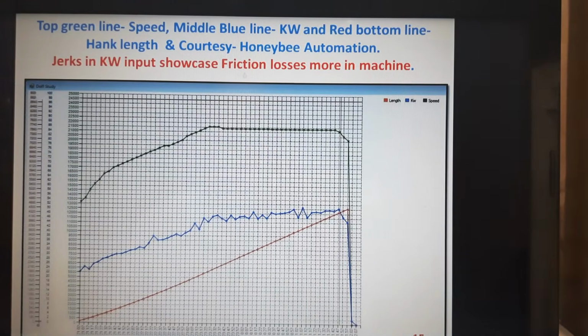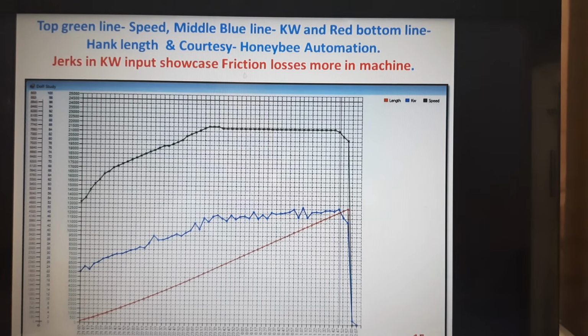Why I talked about the VFD related to the production machine, and what is to be seen in the VFD as well as in the ENMS parameters of each production machine, especially the ring frames. You can see the kinks in the zigzag in the kilowatt because of the jerks or the static friction, or because the friction components are more in the machine, the lack of lubrication and the lack of transmission efficiency. This can be addressed only by monitoring this type of graph for each and every machine. Apart from your production machines, this also needs to be seen in each of the ring frames.